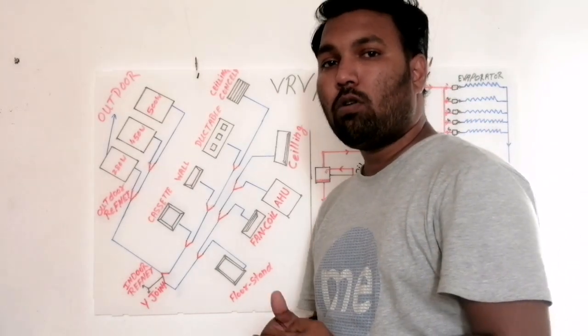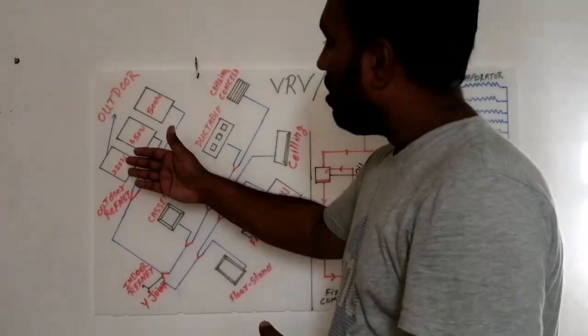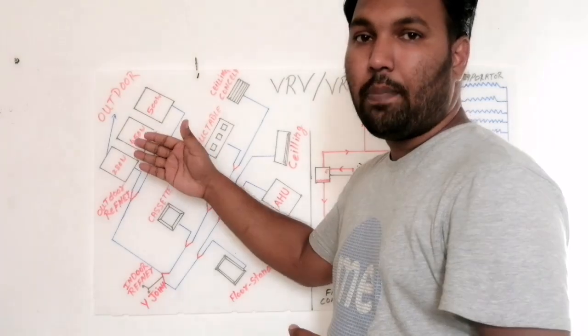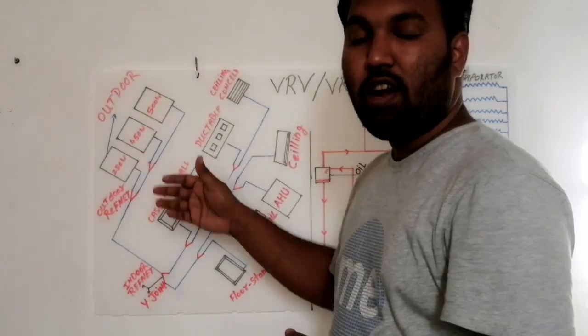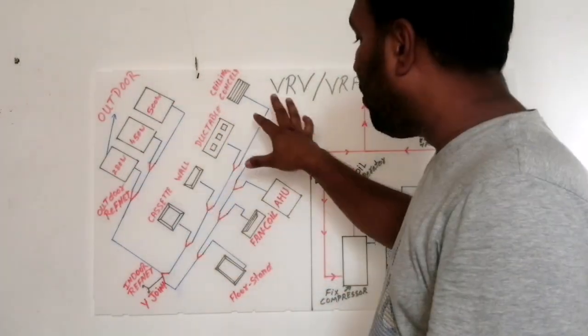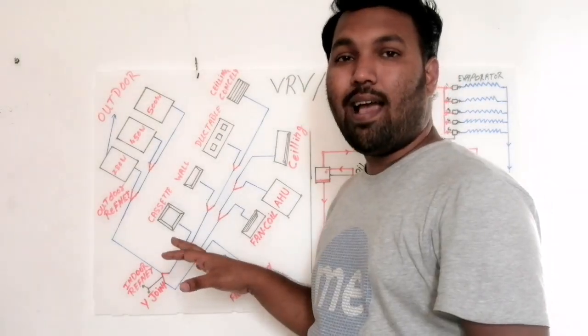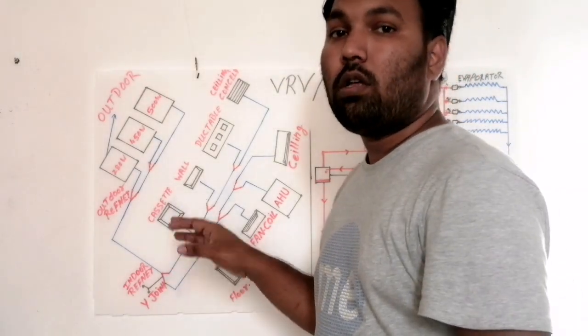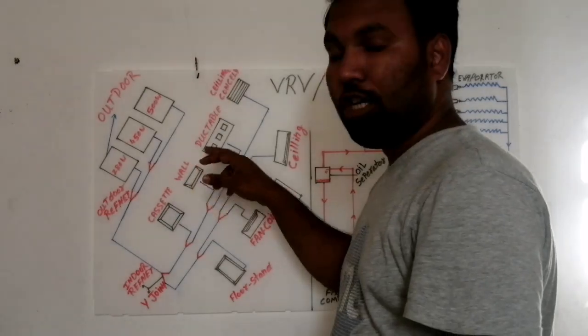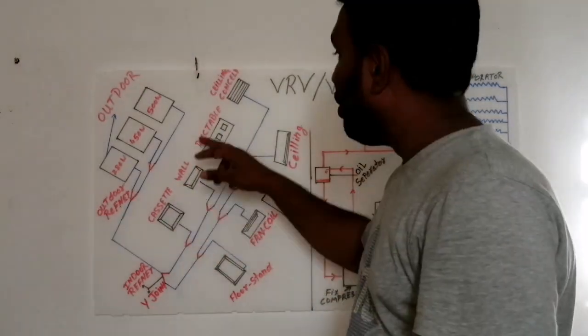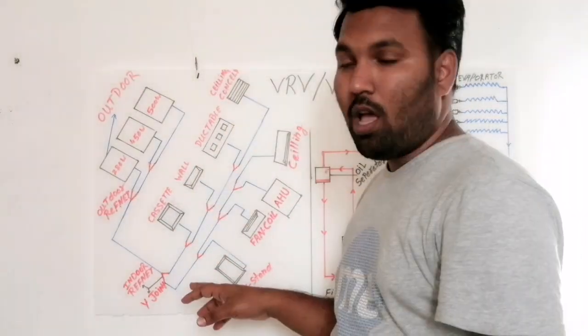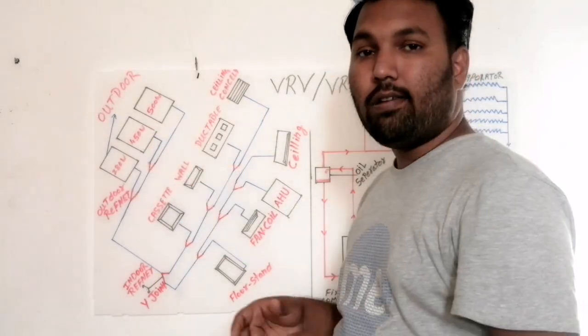If we talk about the wiring and electricity, all these three compressors are three-phase compressors, because we have to provide three-phase supply to all of them. All these indoor units are designed as single phase, like a normal split or inverter air conditioning unit. So for all the indoor units we use single phase, and for all the outdoor units we have to provide three phase.